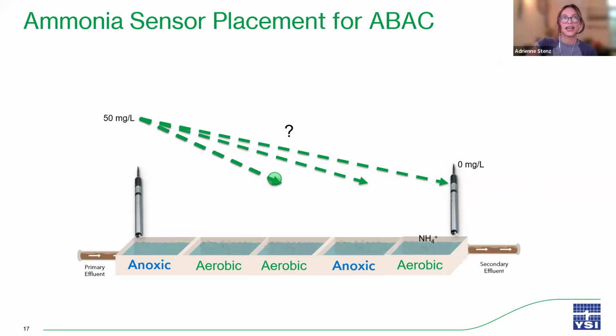So at first, they tested an ammonia sensor in the influent and effluent of each treatment train. In theory, this is attractive because you can monitor the influent ammonia concentrations coming into the basins, and then the effluent ammonium concentrations coming out to ensure that you are removing ammonia from the water and meeting your discharge limits. However, this did not prove to be very effective for them because they found that the effluent ammonia sensor consistently read 0, which does not give much information. Although you can ensure that your ammonia level is near 0 when leaving your basins, it still doesn't tell you anything about how far upstream nitrification may be complete, and therefore is still resulting in excess aeration and wasted energy most likely.